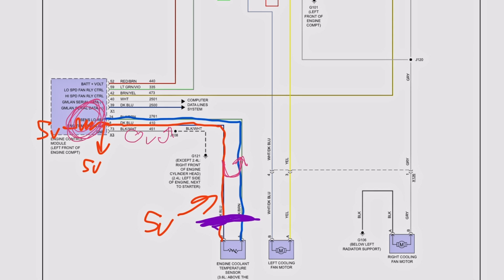So circuit high, circuit low typically indicates a problem—could be in the sensor, could be in the wiring. So how do you know? Well, when we unplug our wiring, we should have 5 volts here on the power side or signal side, and we should have 0 volts on the ground. If that's the case and we have that code, it's very likely the sensor. The other thing you probably want to do when diagnosing whether it's a wiring problem or a sensor problem is back probe at the ECM. And that's a little bit of a topic of debate.